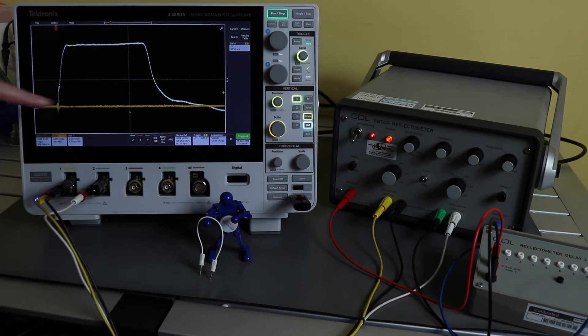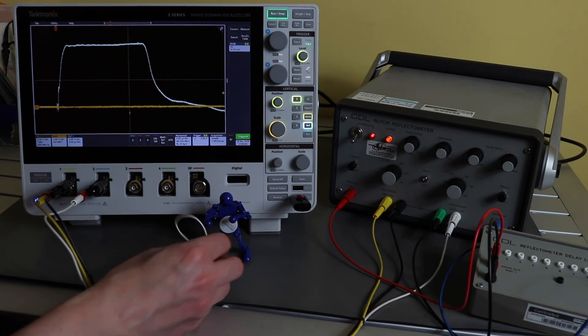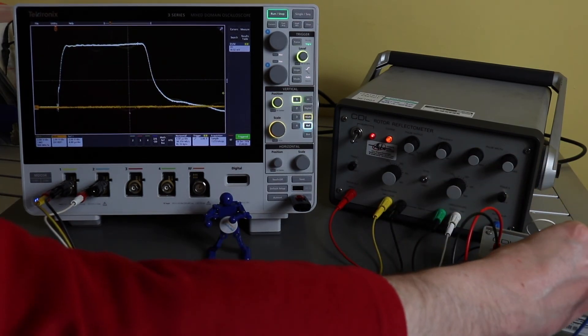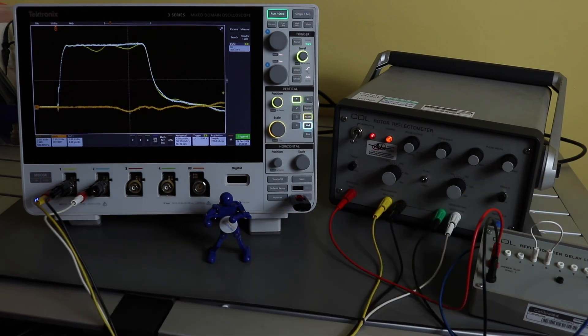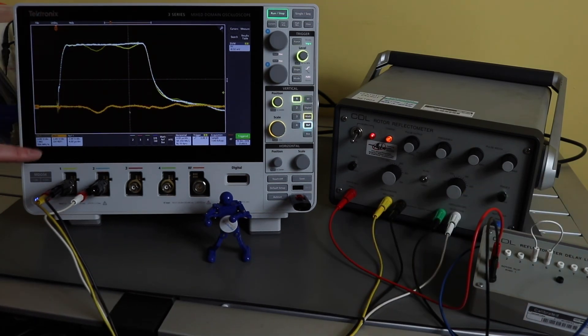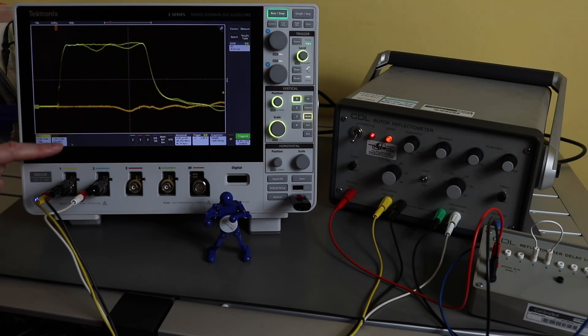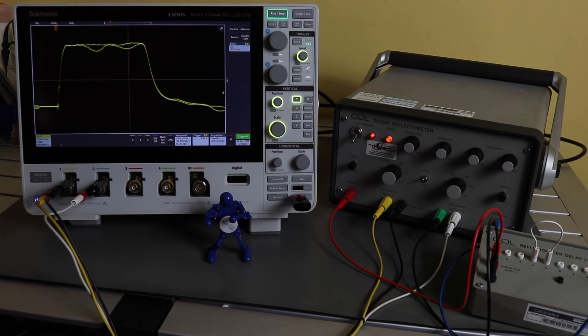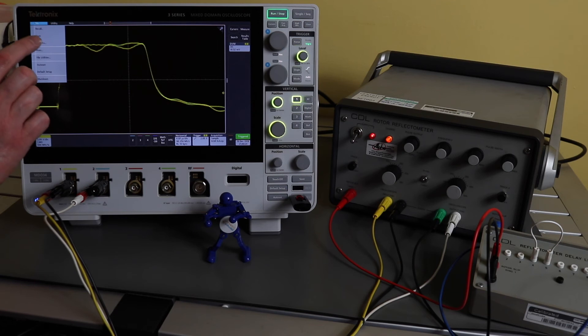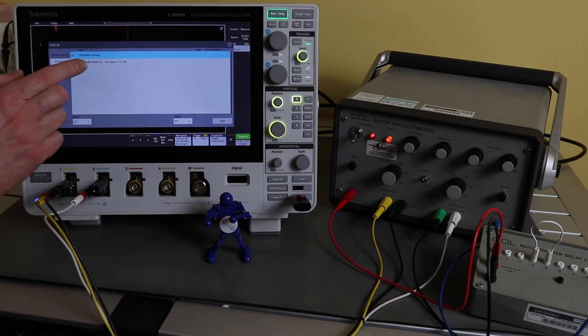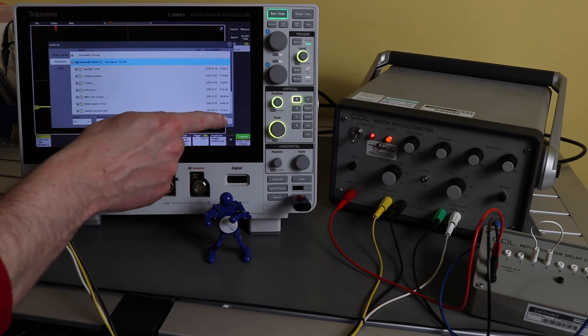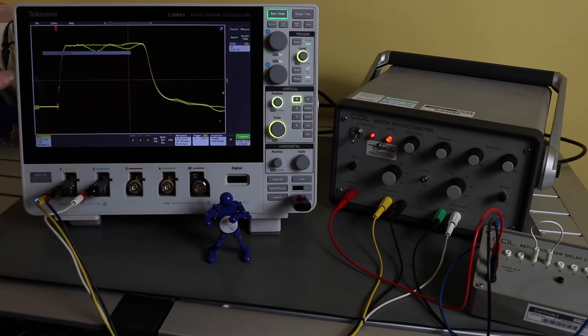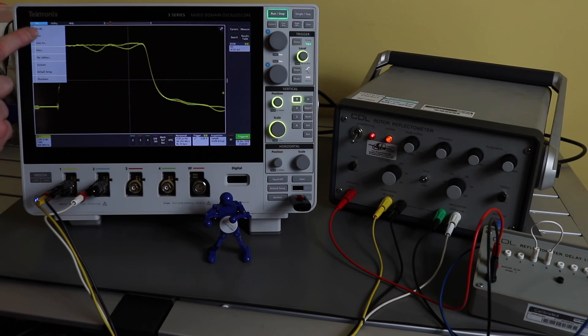So a straight line graph will tell me that there's no defects there. If I put a defect into the delay line, you can see that - in actual fact, I'll take off reference channel - and there you can see there's a double deflection in there. If I wanted to do the maths for this, I would have to re-save one of the channels as a reference waveform. And then recall that.